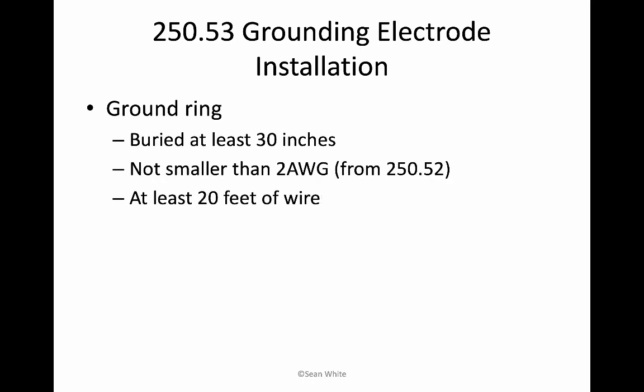We bring this up because it's on the PVIP exam sometimes, and you just should know where to look it up in the NEC. So look at your 250.50, go a little bit further, maybe 3 further. Installation of a grounding electrode, and we're talking about a ground ring, should be buried at least 30 inches, not smaller than a 2-gauge wire, and you need at least 20 feet of wire.